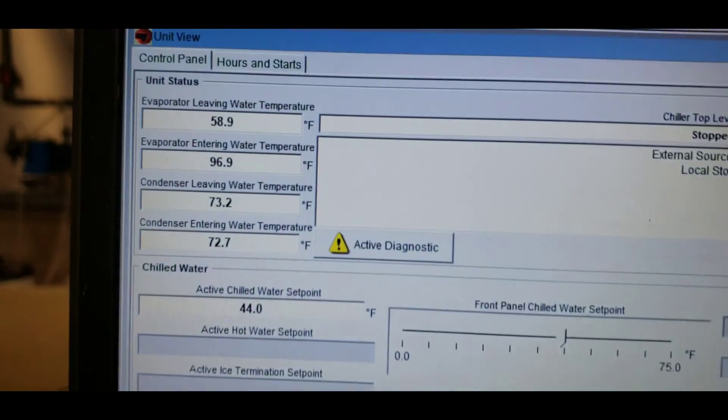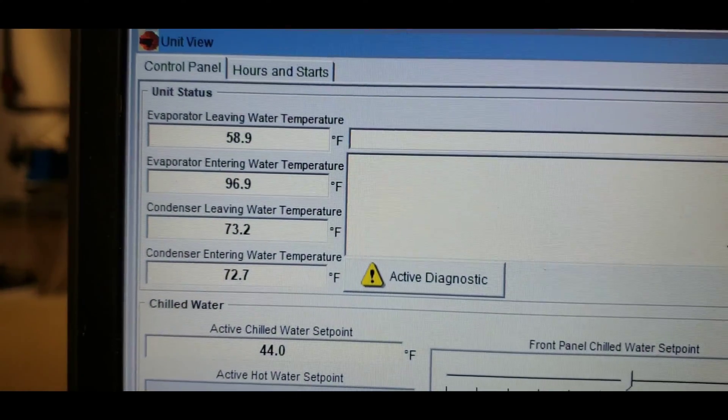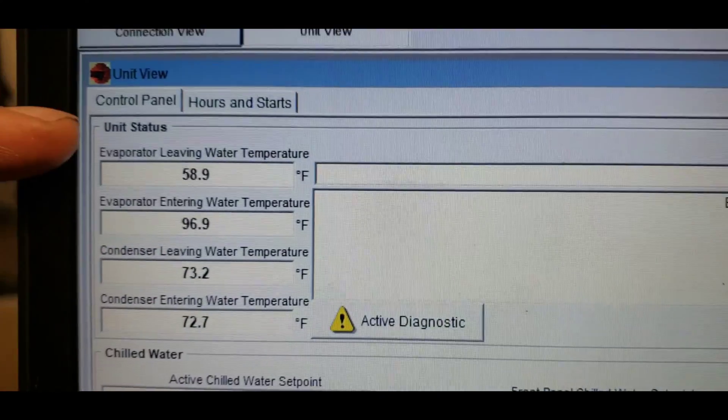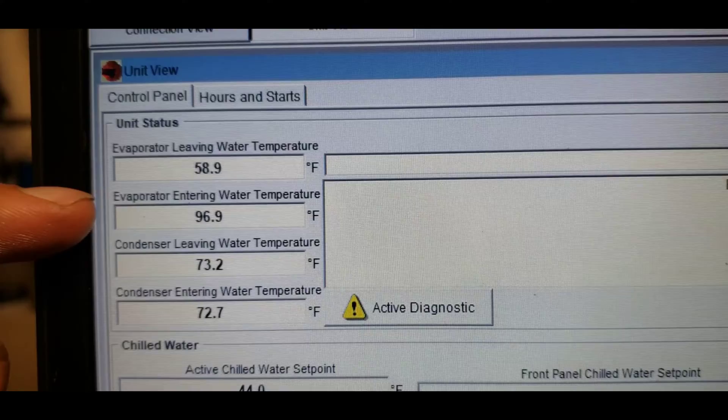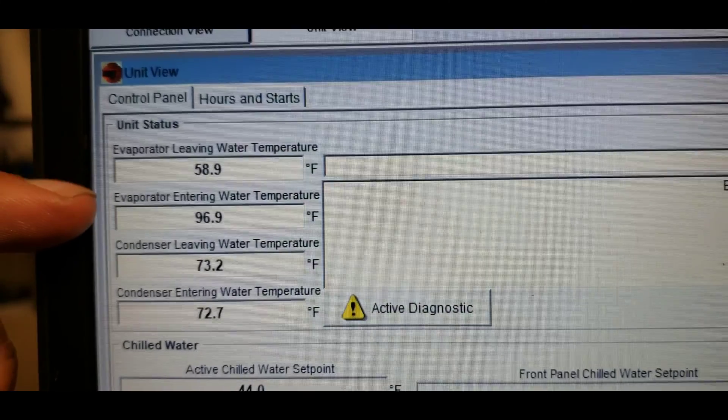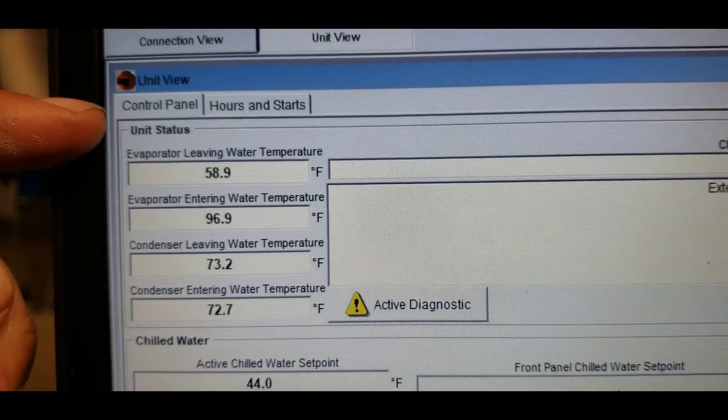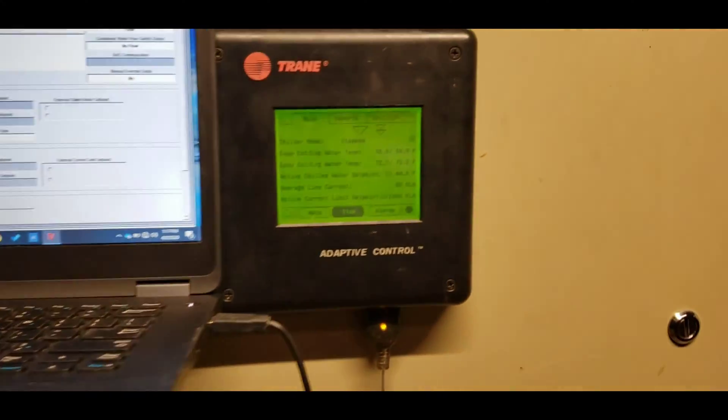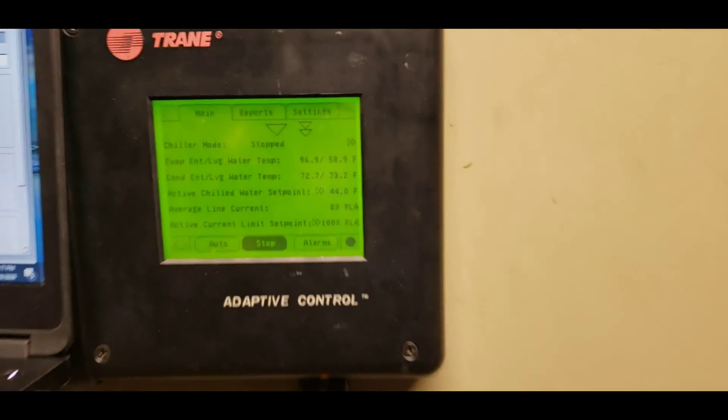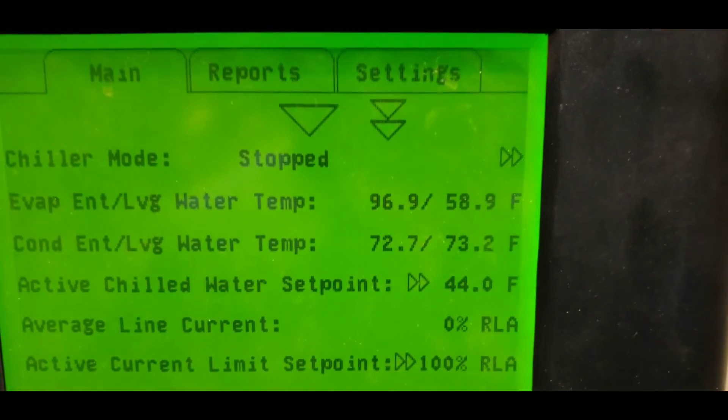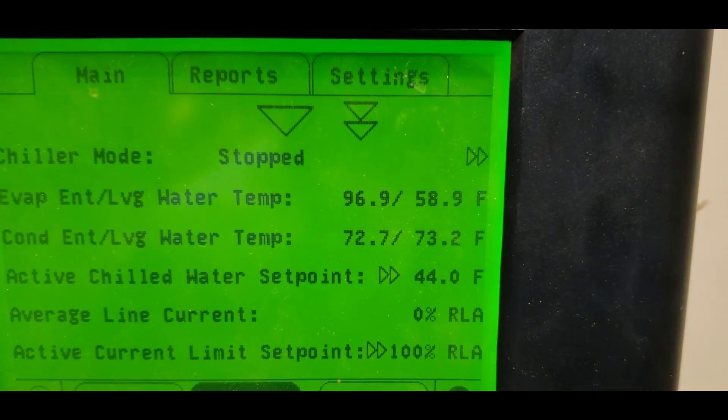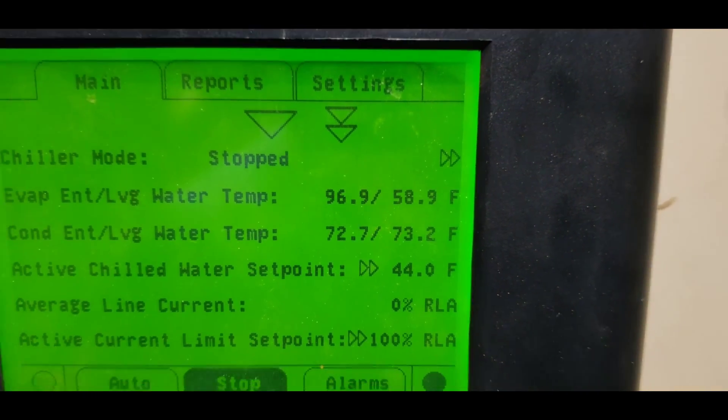On this one, you can see our entering water is at 96, leaving 58. This chiller is not running right now, this is the redundancy. You can see it verifies right there.